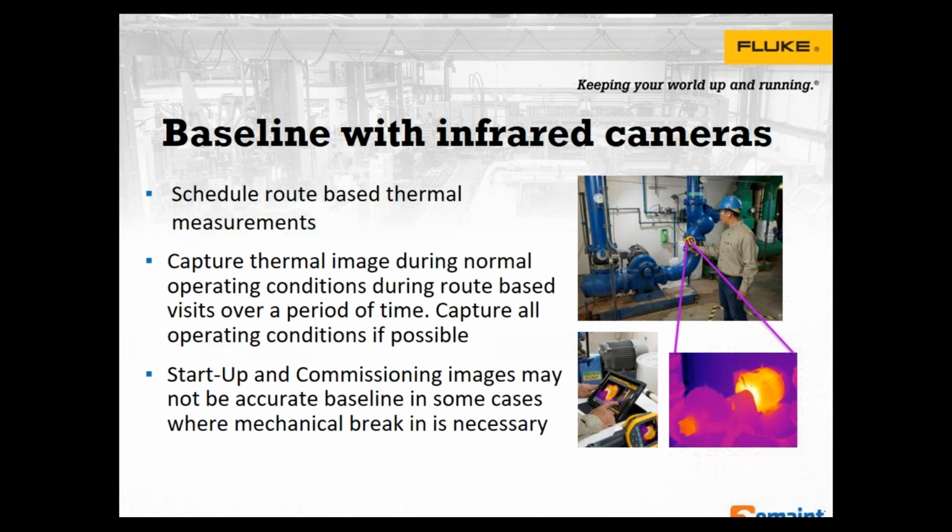The time of day can make a difference too. The time at which you're capturing that particular data is important, because this is just a snapshot in time. It's really the assumption that you're taking this under normal operating conditions. And that's really important, to make sure you know what's going on with the asset at the time the image was taken, and if possible, to capture all operating conditions.